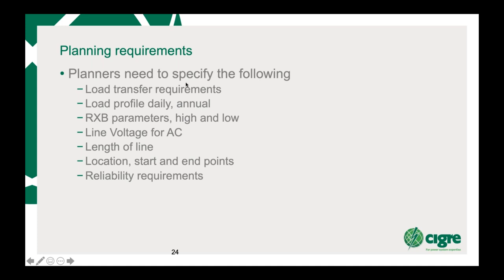what your maximum normal and emergency load is going to be. You also need to have an idea of the daily and annual load flow. Is it a winter peak, summer peak? Is it early morning, midday? Well, what is it going to be? When are we going to hit that big load? And the reason for that is that you can tailor make your thermal rating correctly. So if it's winter and you've got a really cold ambient condition when you hit your high load, you can in fact use either real-time monitoring or a high temperature, and you can actually meter that particular thermal rating for that particular season.